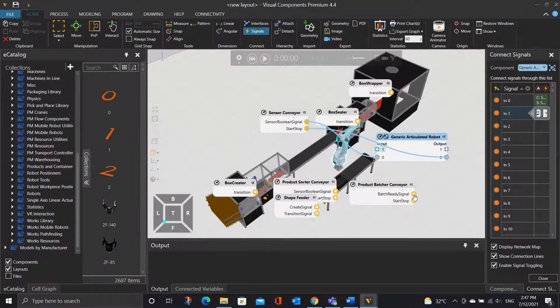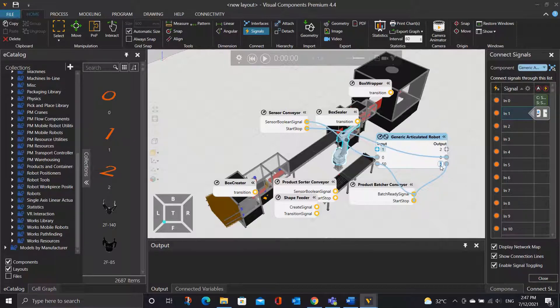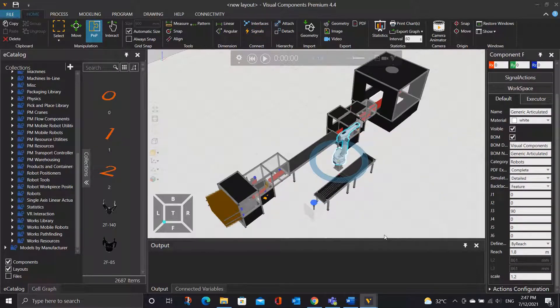Moving forward, we will need to connect the batch-ready signal from the batcher conveyor to the input of the robot, to tell the robot that the object is ready to be picked, and connect the start-stop signal to the output of the robot so that we can have control over the conveyor. We can also change the port number, for example to 50, by double-clicking on it. Now all the signal connections are done. Just click the signal checkbox again to exit the signal connection panel.